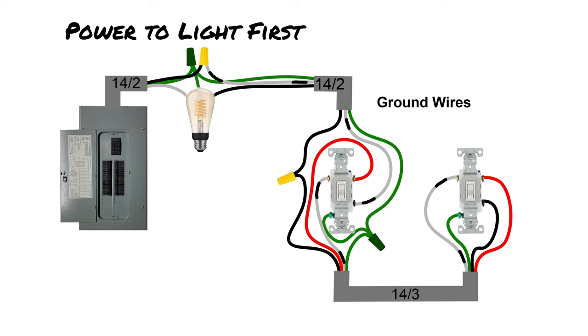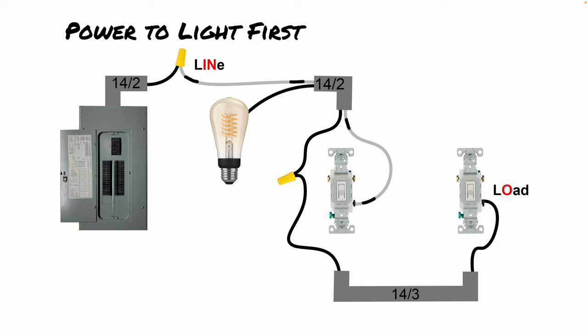Sometimes the power is not coming into a light switch at all — it's actually coming into the light fixtures first. Let's look at this scenario. The line comes from the electrical panel and is spliced in the first box, where it changes from the black wire to a white wire marked with black electrical tape. That white wire marked with black tape comes all the way down to the first light switch and connects to the black screw, also called the common terminal. The load is then connected to the black terminal on the right switch and spliced back to the light fixture.